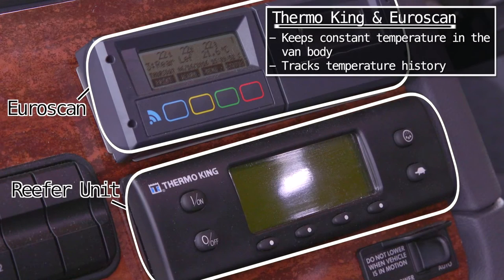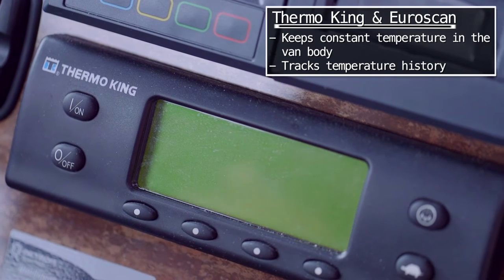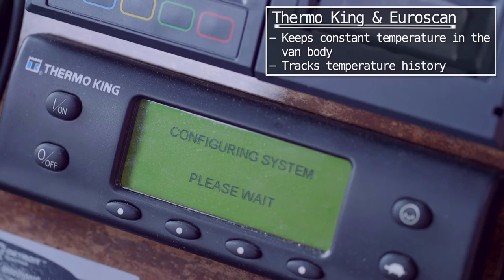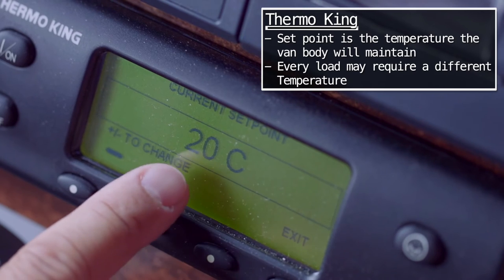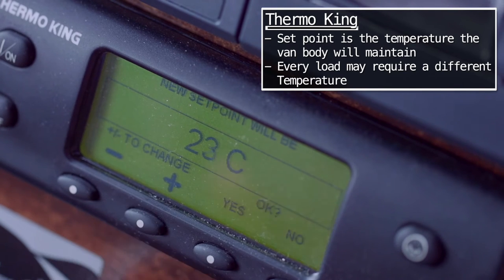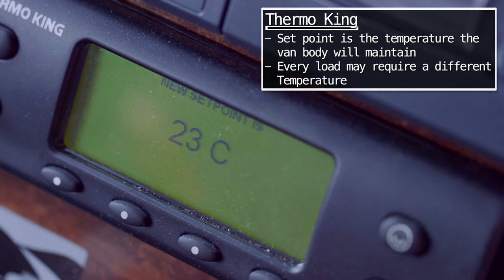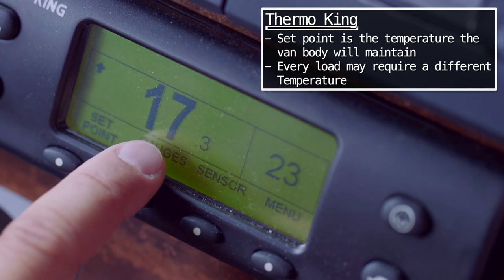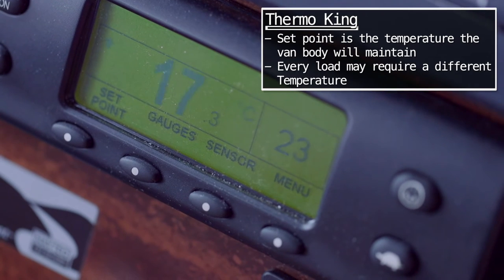The Thermo King reefer unit in the Euro scan from FedEx — turn that on and it's going to go through probably a minute or so of self-checking, making sure it's got the proper coolant, the proper oil, all that type of stuff. Hit the set point button and it's going to pull up what it's set at. Right now it's set at 20 degrees Celsius. You can do plus or minus, so we'll take it to 23. It's now set to 23 degrees Celsius, and currently it's 17 degrees Celsius in the van body.